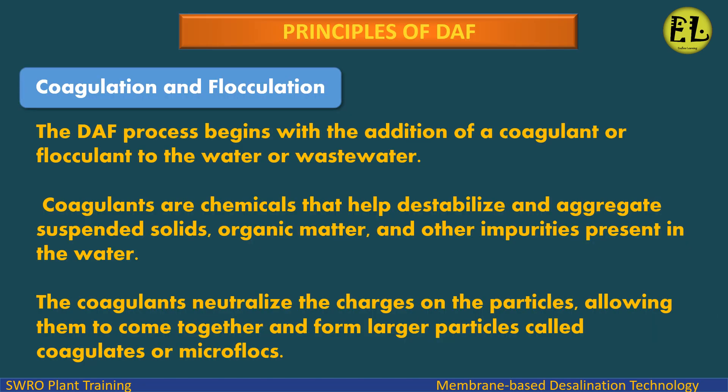Principles of DAF: Coagulation and Flocculation. The DAF process begins with the addition of a coagulant or flocculant to the water or wastewater. Coagulants are chemicals that help destabilize and aggregate suspended solids, organic matter, and other impurities present in the water. The coagulants neutralize the charges on the particles, allowing them to come together and form larger particles called coagulates or microflocs.